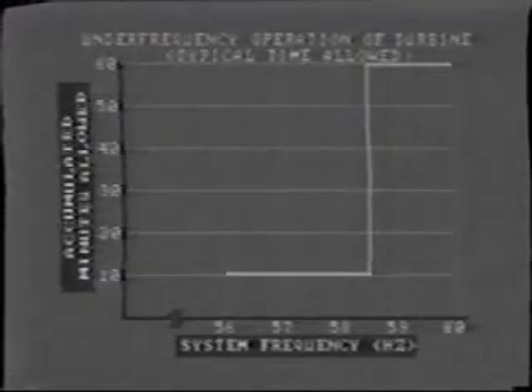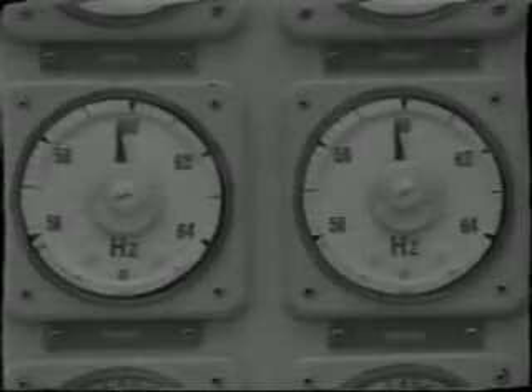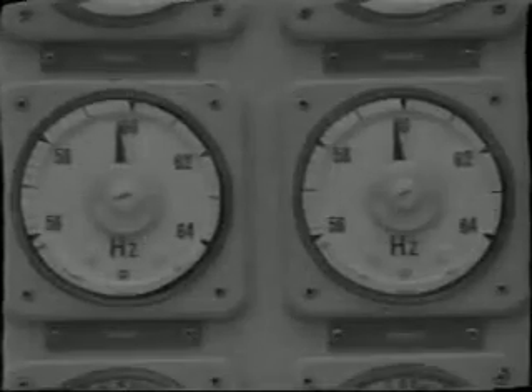Between 56.0 and 58.5 hertz, the accumulated time limit is only 10 minutes. Often on a large generator, a frequency relay will be installed to alarm the operator when the frequency deviates beyond specified limits. In practice, in a large interconnected power system, the frequency rarely falls outside normal limits. However, such an extreme situation can occur if the power system becomes disconnected into separate areas or islands, so that each generator or group of generators is supplying its own block of load.